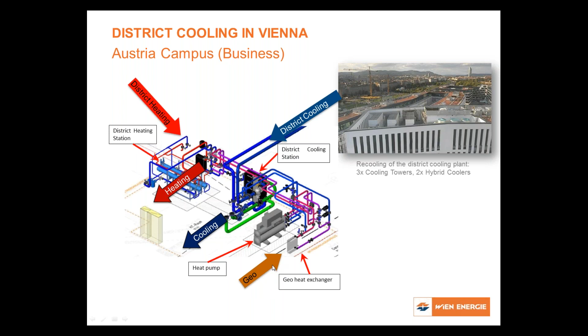This is another project, just a small one, but we wanted to try something. We wanted to support a customer with cooling, and the customer had one really interesting demand: not to have any recooling units on the rooftop. So we tried to do the recooling via our district heating network, as a first pilot project with a cooling demand of 200 kilowatts at 8 degrees.